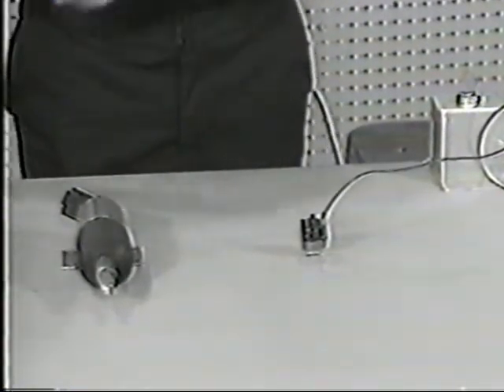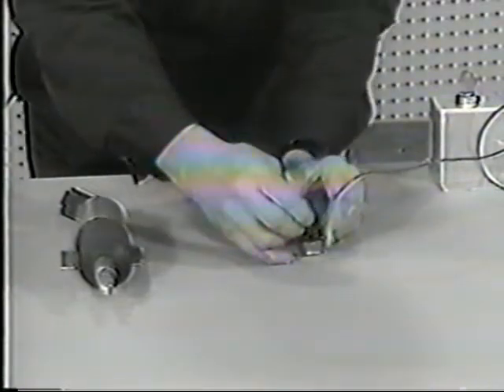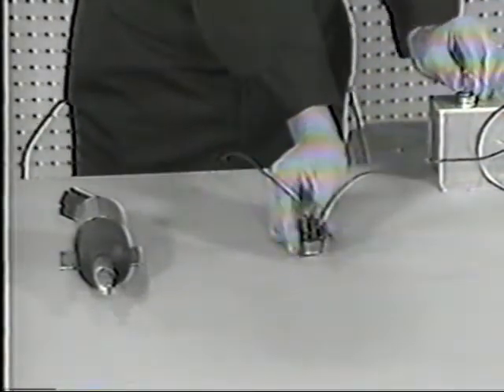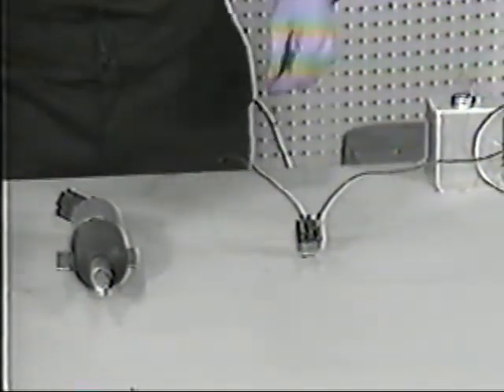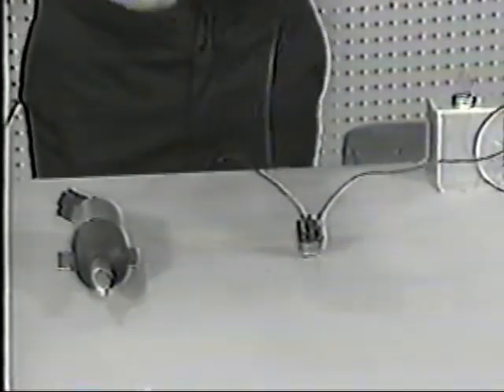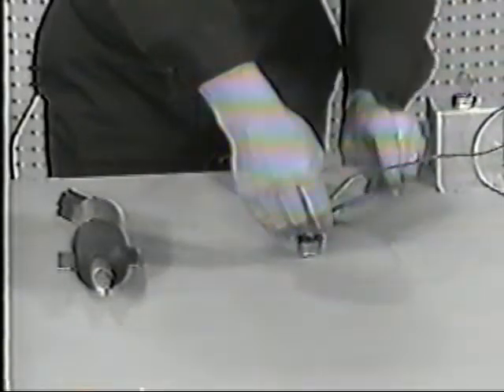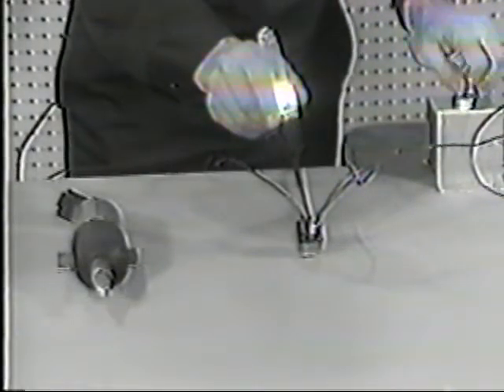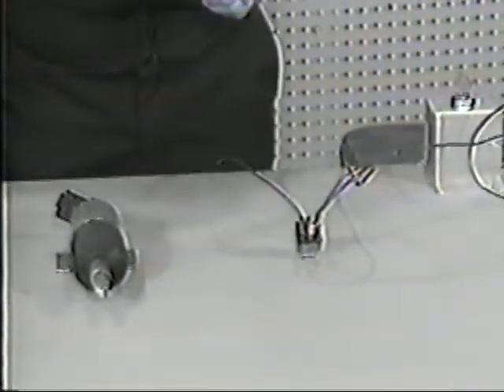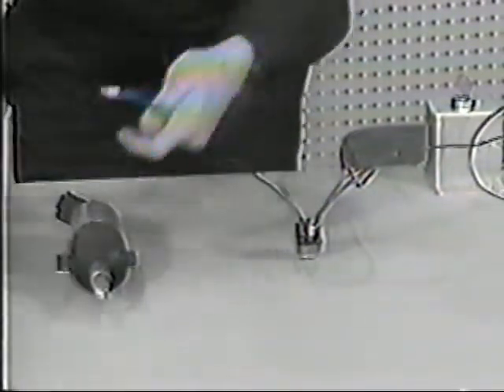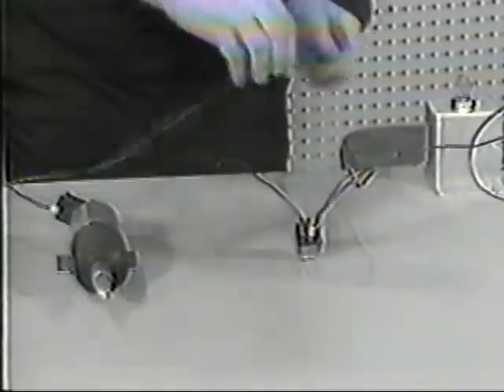Secondly, we'll ground the other control terminal of the relay, and although you probably can't hear it, whenever the key is turned on, the relay clicks. Okay. Thirdly, we'll connect a 12-volt battery supply with a 10-gauge wire to the common terminal on the relay. Now notice that this is hot regardless of whether the key switch is on or off. We'll connect the 10-gauge feed wire for the large fuel solenoid to the normally open terminal on the relay.